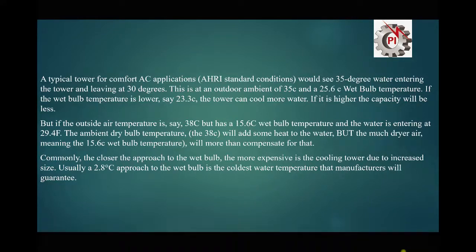Commonly, the closer the approach to the wet bulb temperature, the more expensive the cooling tower due to increased size. Usually a 2.8°C approach to the wet bulb is the coldest water temperature that a manufacturer will guarantee.